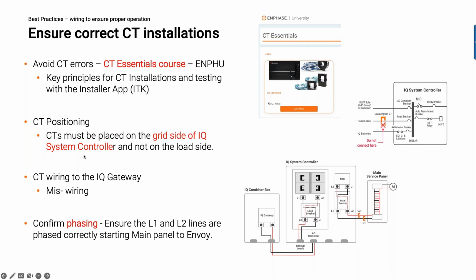This is just one of those errors that occurs when installers are thinking, okay, I just want to measure consumption from my loads. To do that, you tend to want to put them on the load side, and that would be incorrect. It needs to go on the supply side to catch all of the energy that's coming into the home. CT wiring to the gateway, a lot of miswired gateways. That needs to be checked. And this is all covered in CT Essentials as well.